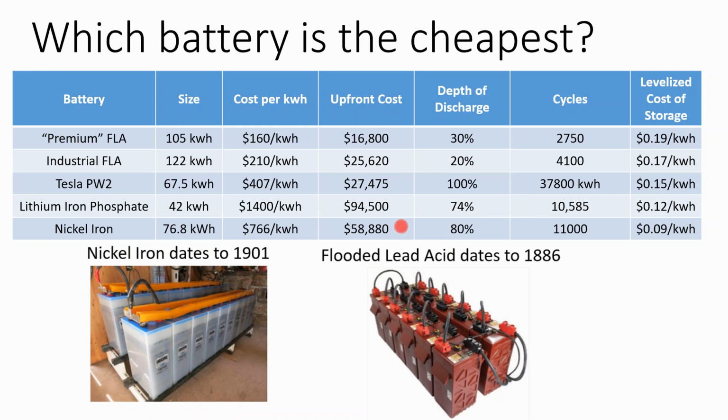And when we got down to it, we were going to choose between the industrial FLA and the nickel iron. It was the capital cost where the client said, I'd rather have an 11-year battery rather than a 30-year battery. I don't want a starter battery. I don't want a battery that I'm going to have to replace in 5 years, but I don't want a 30-year battery either. I'd rather see what the technology is going to be like at the end of the line.